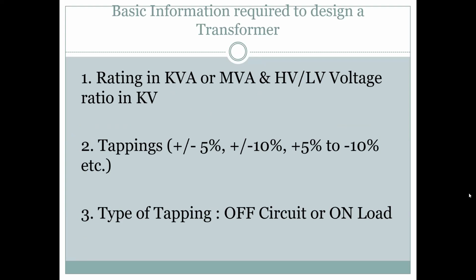Now, about the basic information required when you design it: as I said, transformer manufacturers do not decide the rating of the transformers, because transformer users know what the load is. Here AC is running, lift is running. The lift motor has so many starts and stops, so many reversals of direction. Somewhere some abnormal phenomena is taking place. All these have to be calculated and the load requirement taken care of.